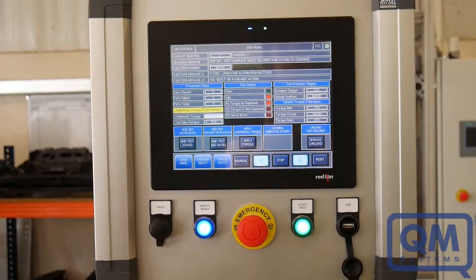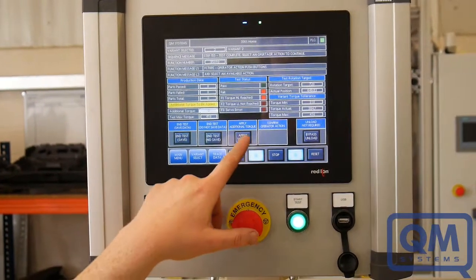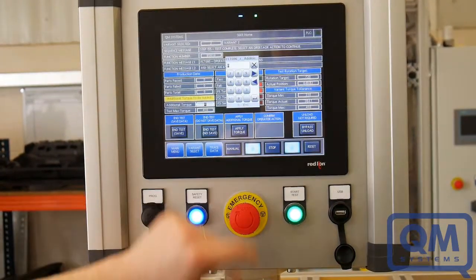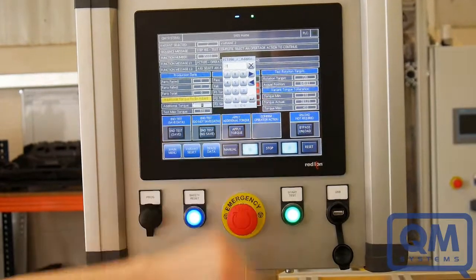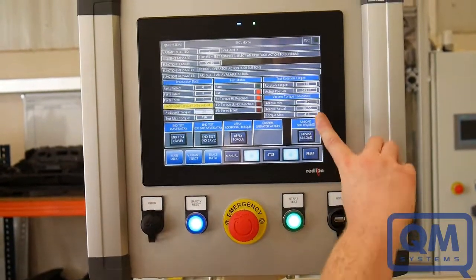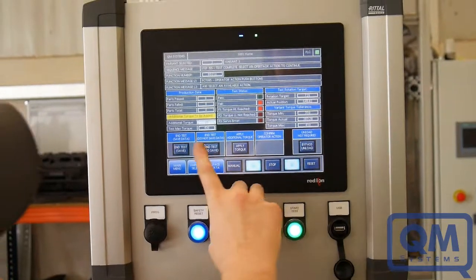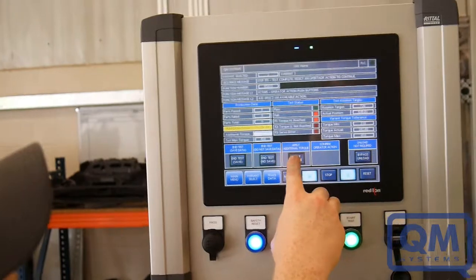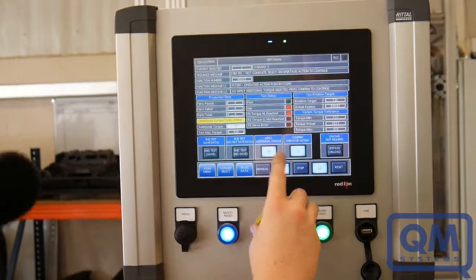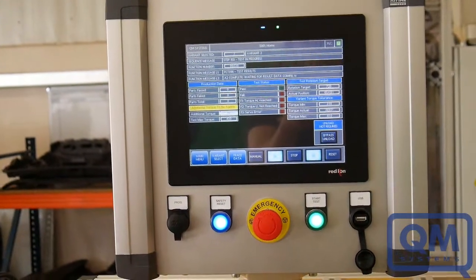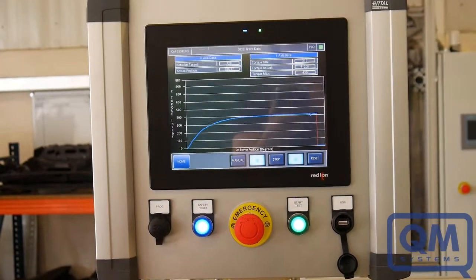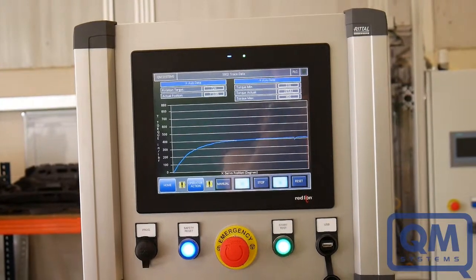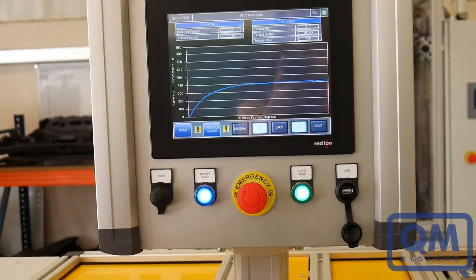If there's rotation remaining that we can still test, then the operator has the option to apply extra torque. In this case, if we say we want to apply an extra 20 to the torque, our recipe target remains at 410, although our maximum test target has now gone to 430, and the operator has to apply extra torque and press confirm to continue. If we press confirm, the test is still in progress and continuing. And this time we've actually reached our target position.